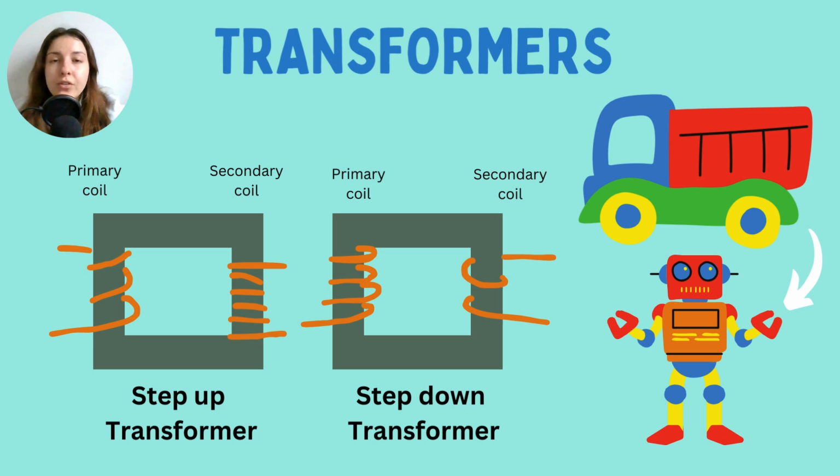Because the electricity is being transferred over a huge distance, remember the national grid supplies electricity to the entire country, we have to transmit alternating current to a very widespread area. We want to make sure that it's very efficient. I did do a video about alternating and direct current, and how that came about, so I'll link that for you. So the transformer at the very beginning is a step up transformer because it's trying to increase the voltage to decrease the current and reduce the inefficiencies and heat that is transferred to the surroundings.